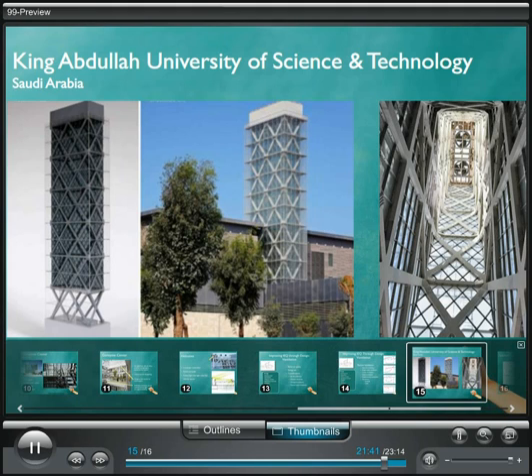A prominent passive feature of KAUST includes two 195-foot-tall solar towers. The glazed solar towers provide ventilation for the courtyard spaces between the lab clusters. The design also ensures that the air discharged from labs, which could be contaminated, does not go back into the buildings. The towers act as chimneys in which the sun and wind work together to draw contaminated air out. Dampers located near the top of the towers regulate airflow and prevent downdraft in negative pressure conditions. Fans provide supplemental airflow under extreme demands. The labs also utilize a heat recovery ventilation system to provide fresh air while saving energy.